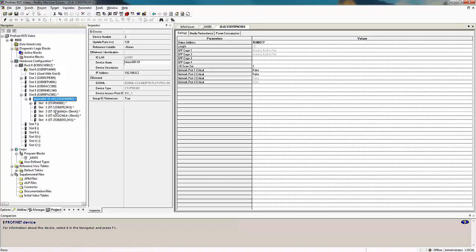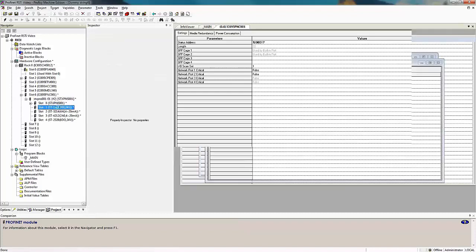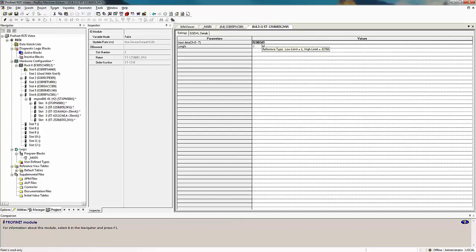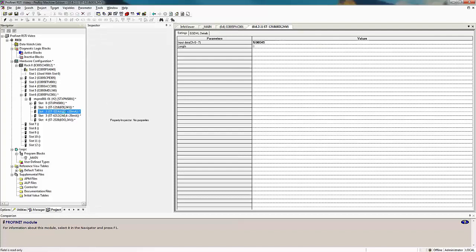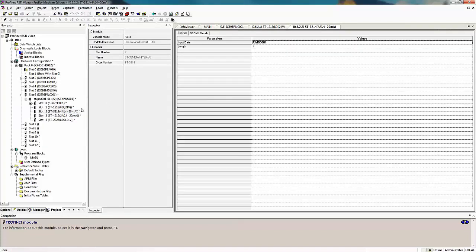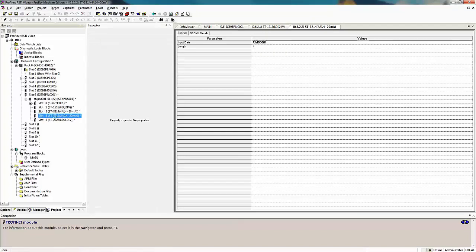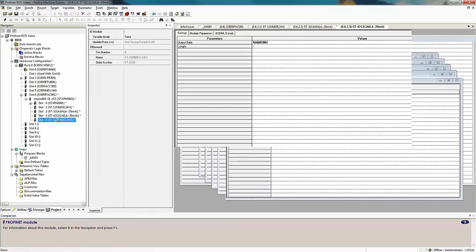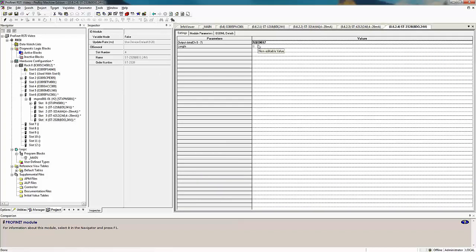At this point we need to double click on our modules to check the reference addresses that were assigned to each of them. For example, on my input module it's taking up reference address %I49 with a length of 8. My analog input module is starting at analog input %AI1 with a length of 4. My analog output is %AQ1 with a length of 2. And finally my discrete output is %Q17 with a length of 8.